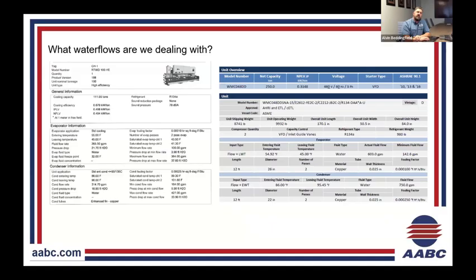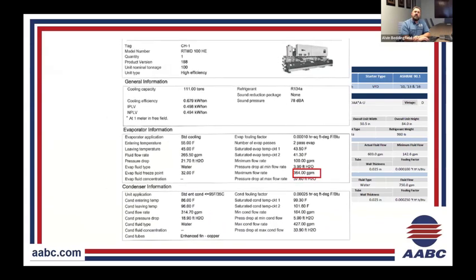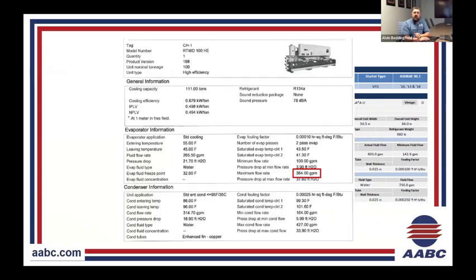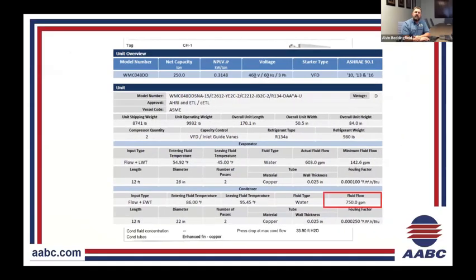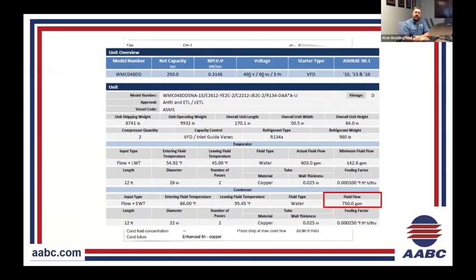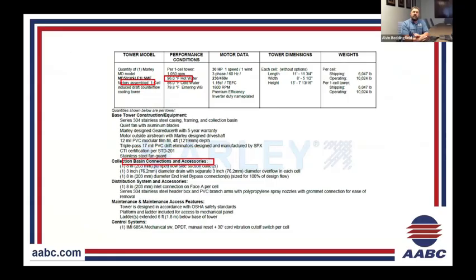So looking at the two chillers, obviously one was an existing chiller and one was a new chiller. So let's establish where our flow's at first, right? So the flow is going to be, okay, 364 on the first cooling tower, and then we'll dive into the next one at 790 or 750, right? So we got our two flows. Okay, now what's the cooling tower? Once again, let's look at the way the cooling tower is designed.